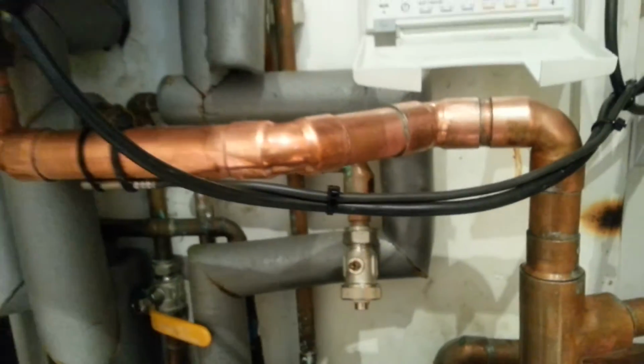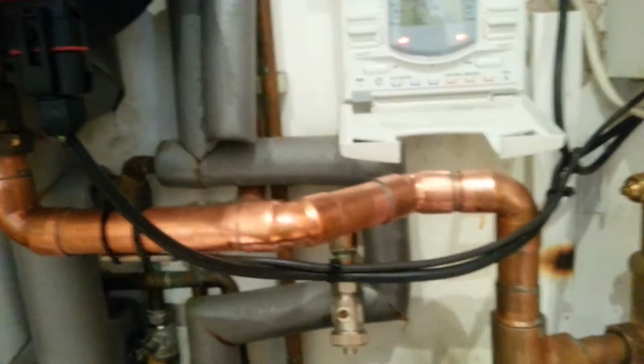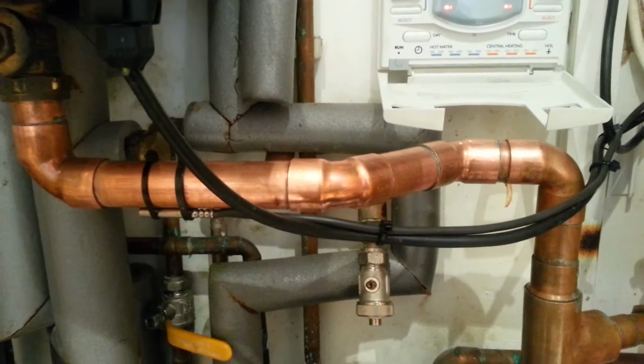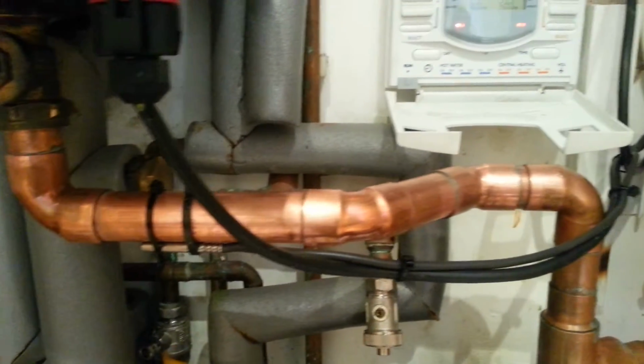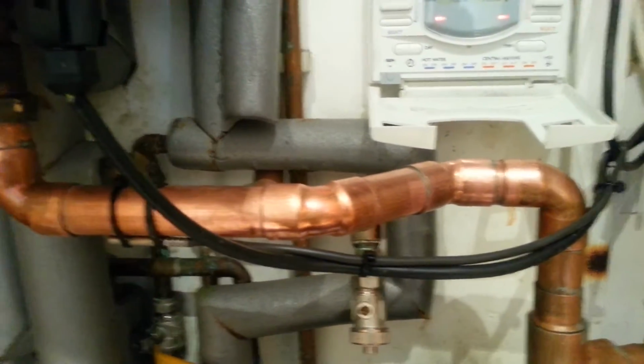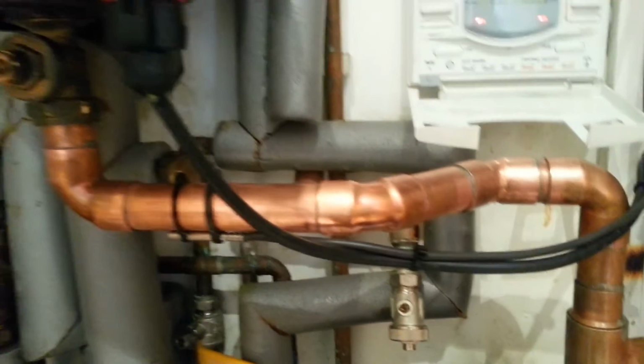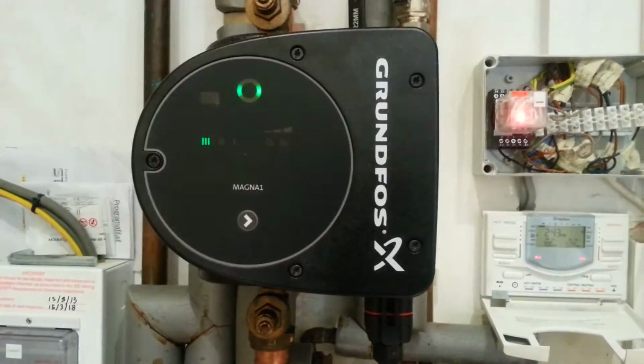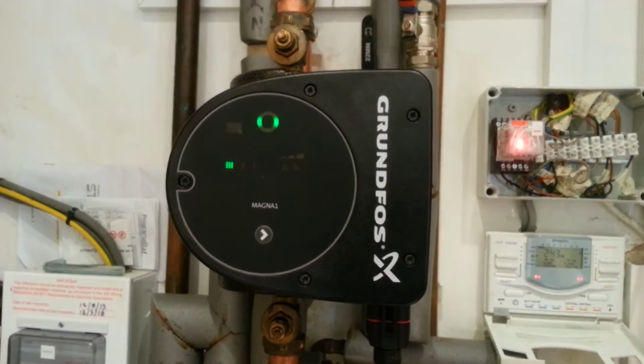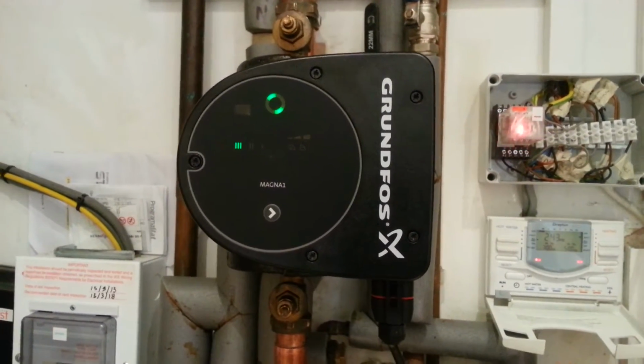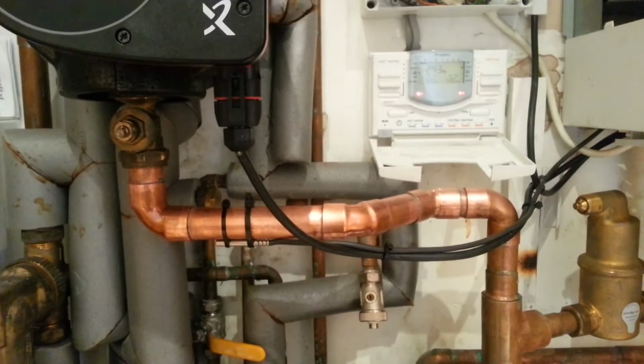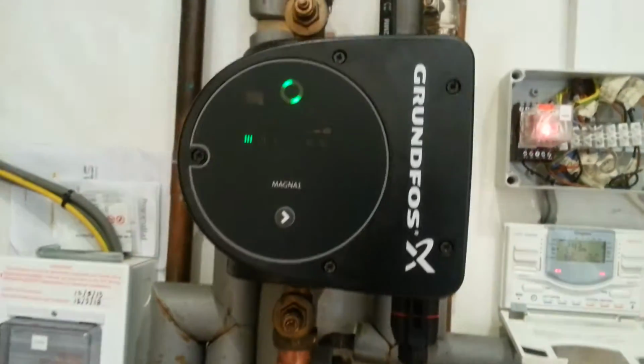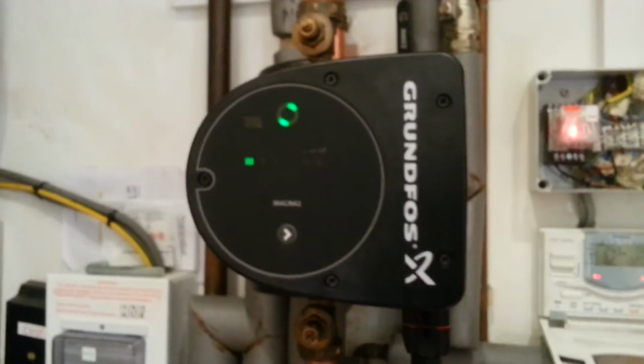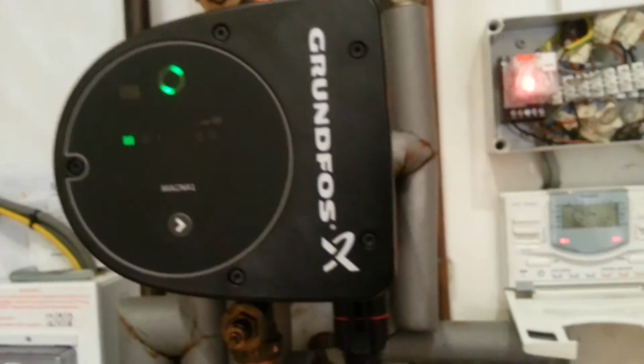So the problem I had originally was I'd fitted a smaller pump on the original conversion. And what I didn't realise was there's about 30 or 40 metres equivalent length of pipework to both of the hot water cylinders upstairs. So the pump just wasn't man enough to deal with that. So I've changed it for a Magna 2580, and we're getting flow rate through the upper cylinder now of about 14 litres a minute, which should drop about 14 kilowatts or so through the coil. And that would be at probably about delta T 13, 14.